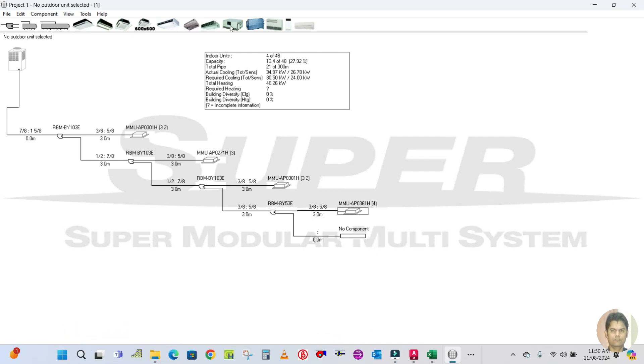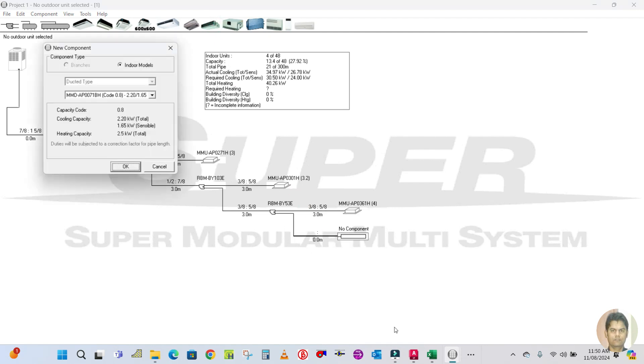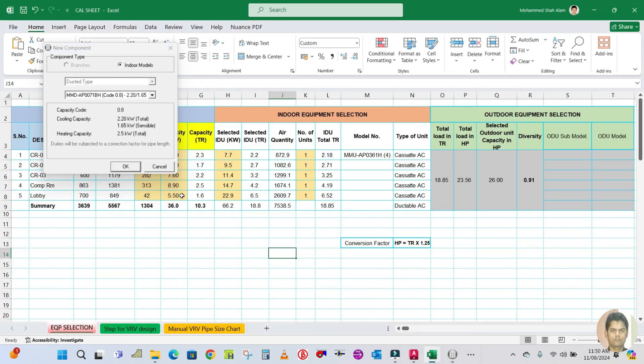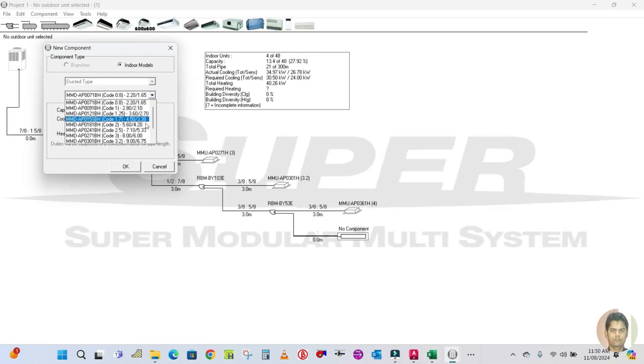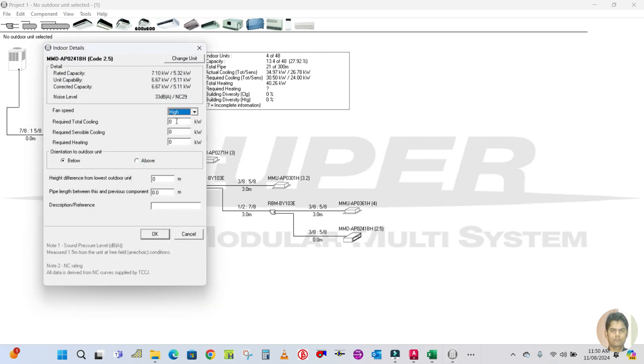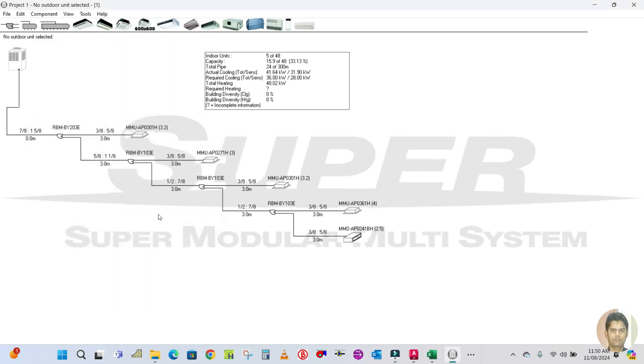The last unit is a ductable unit. Select ducted type — ducted higher static. The required cooling capacity is 5.5 kilowatts, so select the 7 kilowatt unit. Enter required cooling capacity 5.5, sensible 4. Pipe length is 3 meters here and also 3 meters for the previous component. Click OK. All indoor units are now placed.